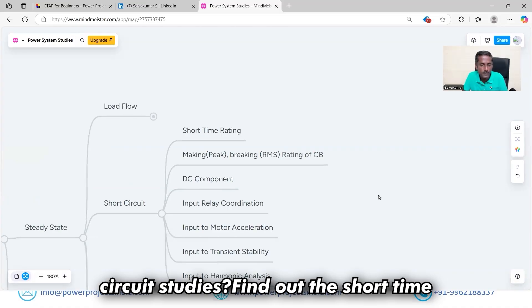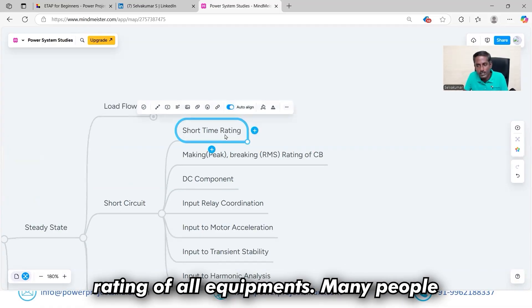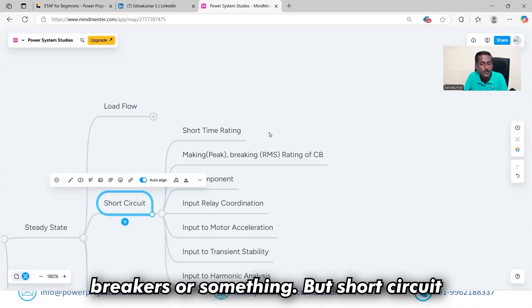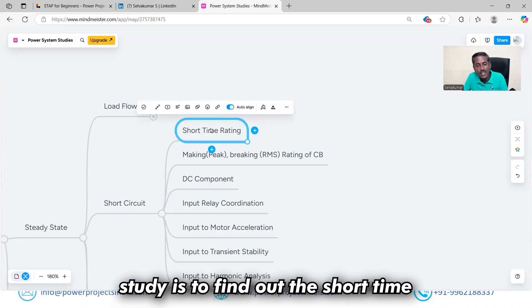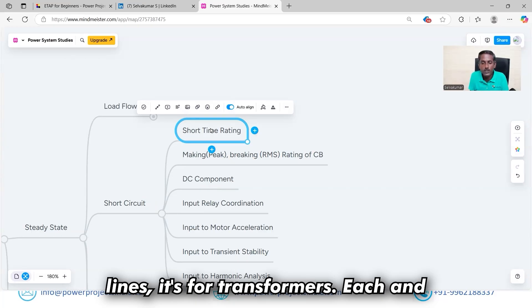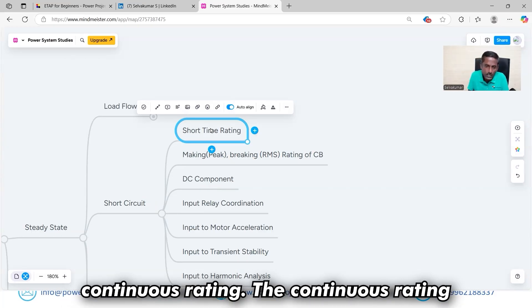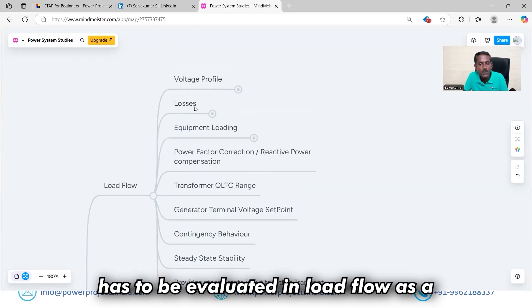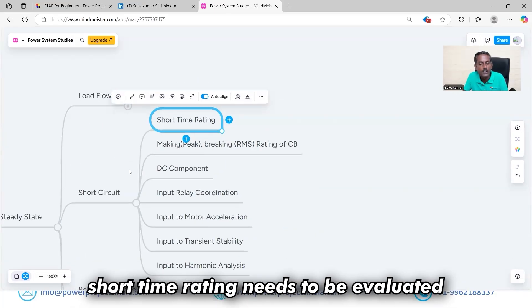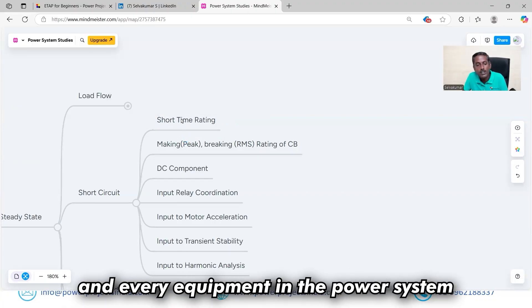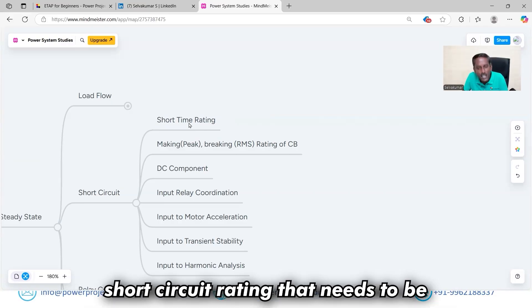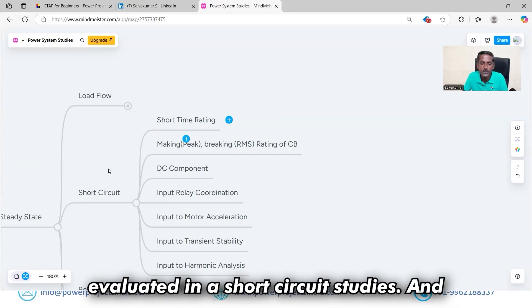Why do we need to perform short circuit studies? Many people think short circuit study is needed only for protective devices like circuit breakers, but it is to find out the short-time rating of all equipment — cables, switchgear, transmission lines, transformers. Each equipment has a continuous rating evaluated in load flow for equipment loading, and a short-time rating that needs to be evaluated in short circuit studies.